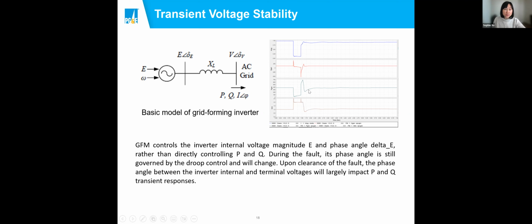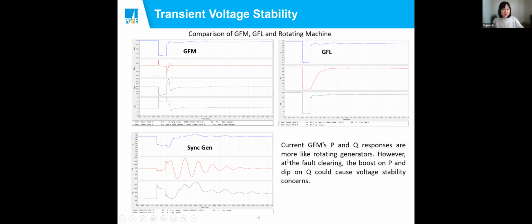Another feature that I want to bring to everyone's attention is that you can see the grid forming inverter upon fault clearing could be providing an overshoot and a very, very quick boost on the real power. And the reactive power actually went down before it goes up. Again, I think this is potentially driven by the change of the magnitude and the angle of the internal voltage, and that drives the performance like this. We're going to talk more about that performance later.